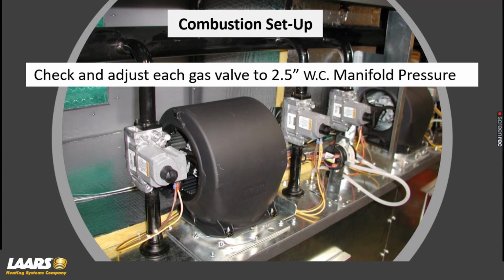Keep in mind, if your valve is not energized, and I put a manometer on it, my blower starts up, I could be reading blower pressure from the chamber. Why? Because once we put air into that chamber, it could travel backwards through the burner, into the orifice, up the manifold to the bottom side of the gas valve. All right. So when you're measuring 2.5 inches, your gas valves need to be in the on position. And I did simulate that in the video.